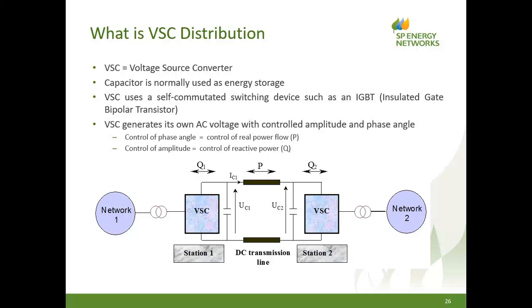So just like a synchronous machine, we can generate power, import or export as we will, and we can generate reactive power, both absorption and generation as we will. So we have all of the functionality of a synchronous machine, as I say, without inertia and without rotational mass. That is the simple principle of a voltage source converter. Two inverters separated by a transmission line, which can be overhead line or cable. And as Kevin has explained, we have both in this particular application.